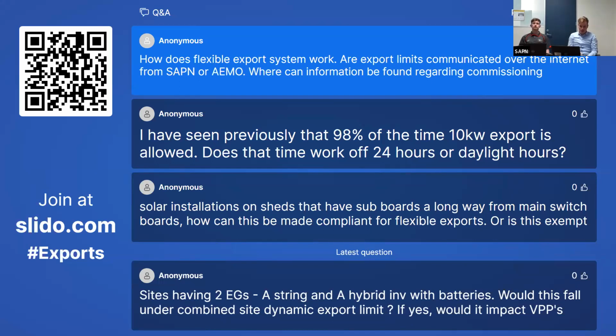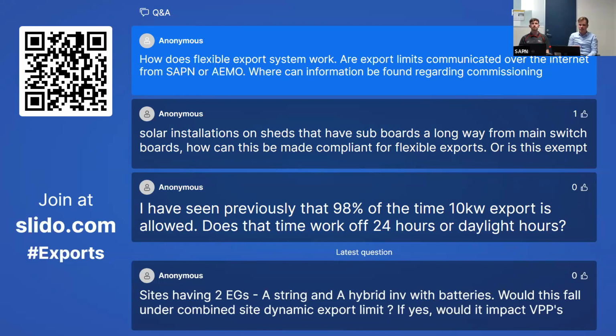So it comes from SA Power Networks, the export limits, and they're calculated based on the conditions of the local network at that point in time to maximize the capacity that we make available to customers. In system emergency conditions, for example back in November last year, where we were islanded from the Victorian power system in South Australia, and there were times of system security risk, sometimes AEMO does direct SA Power Networks to reduce the output from solar. And in those cases, we would put a manual intervention over those automatically calculated export limits during those periods to reduce the output of solar systems to keep the system stable.